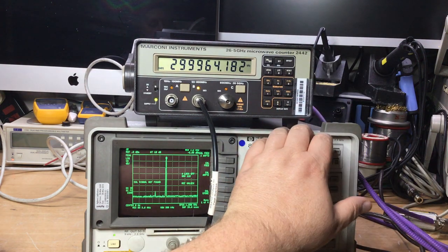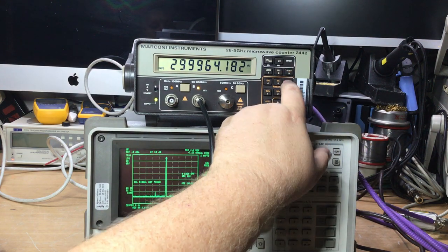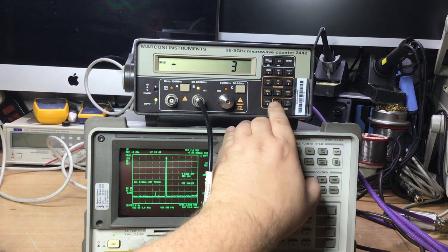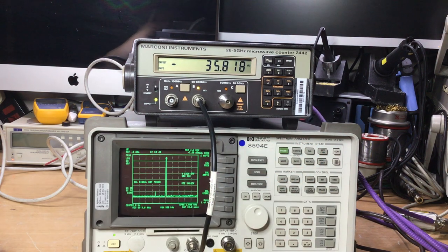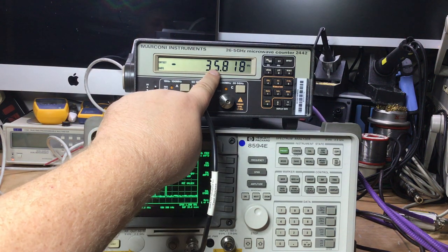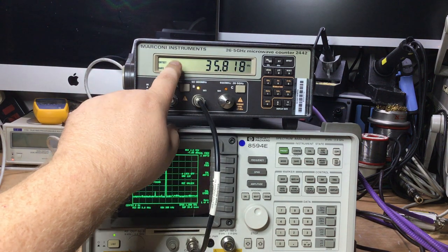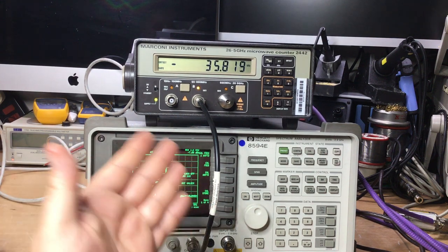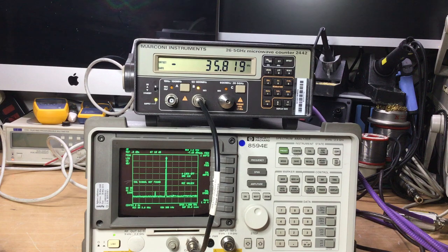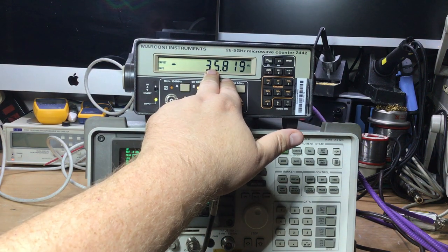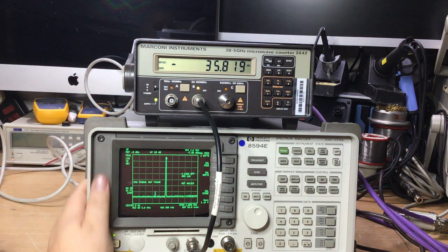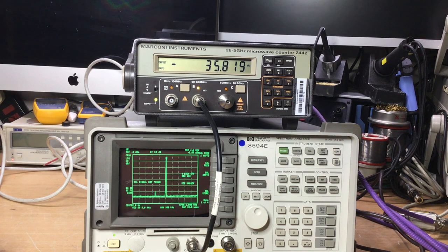So what I'm going to do to find out the actual correct frequency offset that it's currently at the moment, the calibrate signal, if I press set button and then type in 300 and then set again, that should tell us then, because we set the frequency counter to a reference frequency of 300 megahertz, it will now display what the frequency error is, which in this case is 35.818 kilohertz minus. So the frequency is lower than 300 megahertz, obviously, because it was 299 megahertz. So this is a very, very accurate frequency counter. So we're going to need to adjust this 35 kilohertz down to zeros, near as damn it zeros, so that therefore this reflects the accuracy of the spectrum analyzer.